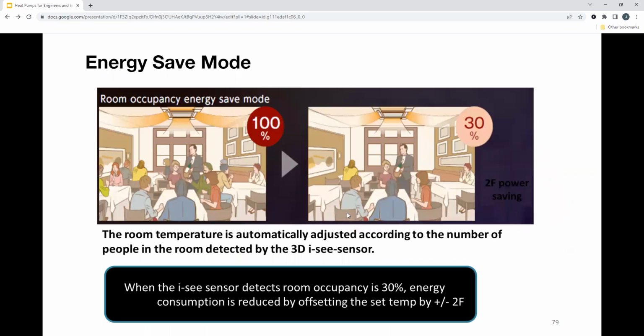In this case, that's what I'm talking about. You have that sensor up here. It can tell the difference between 100% occupied, right, versus about 30% occupied. And you can adjust the system accordingly to the percentage of the room. So in this case, if there's about 30%, the offsetting temperature is ±2, depending on the room.